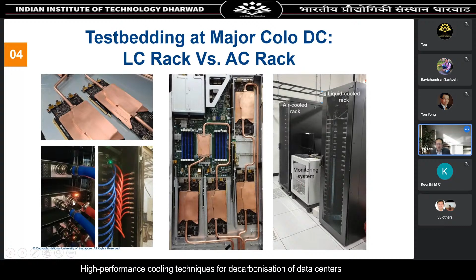These are some pictures showing the test bed we did with a major co-location data center. We had an air cool rack, a conventional rack using exactly the same servers, versus a liquid cool rack with the same servers, except we removed all the server fans and retrofitted our liquid cold plates, as shown here. These are the dripless quick connectors that allow easy coupling between the manifolds and the servers.